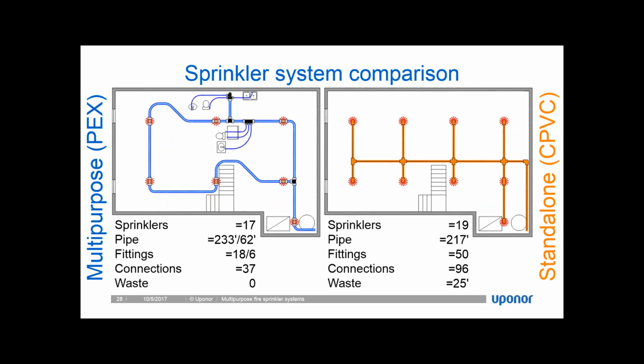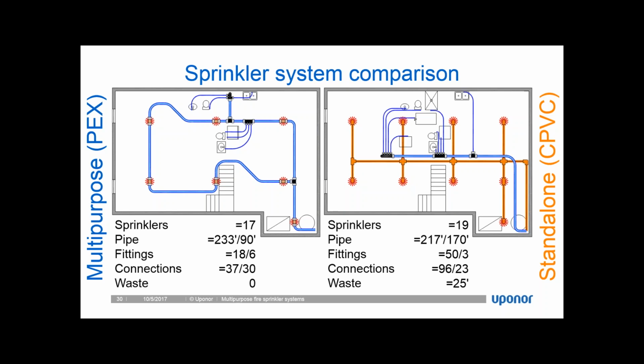So on the standalone side, we're not going to be tying into any lines because it's a standalone system. So I've got standalone sprinklers. I also have standalone plumbing. Because I don't have to really concern myself with circulating water anywhere in the system, I'm just going to install all of the plumbing fixtures from below. Because of that, I'm going to have a lot more piping for my supply lines. So I'm doubling up on my supply lines when I have to install these in a standalone application.